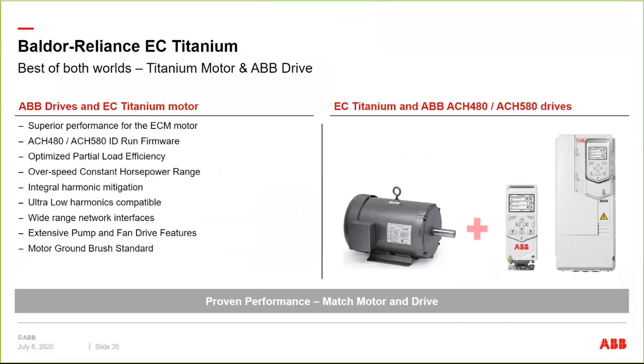Now, I said that you have to manually set these up with the parameters. However, I started this presentation by saying ABB is a drives company and knows our motors and how to control them. So there is a release of the firmware for the ACH 480 and 580 that will do the ID run. And you don't have to set up anything. So if you're going to be running it on an ABB drive, the ID run will run the motor just fine, and you don't have to manually put in these parameters.